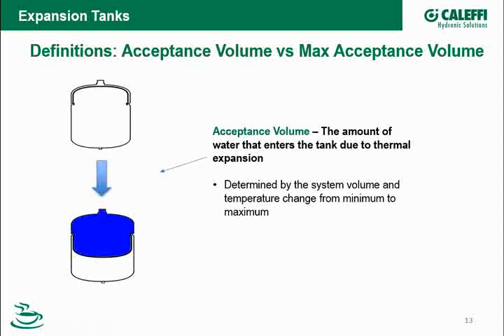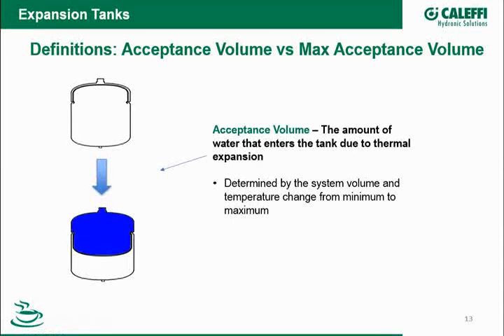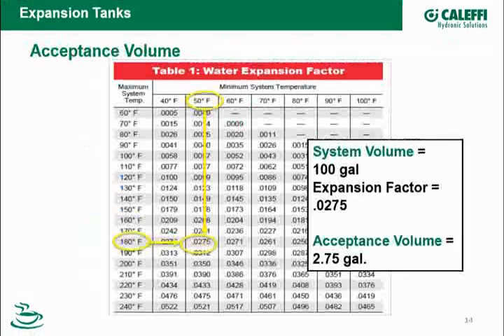Or the volume of water that's going to be generated by that expansion. For instance, this is a water expansion factor chart. Off of this chart, I look at various minimum water temperatures and various maximum water temperatures. For my example, let's say I'm heating the water from 50 degrees Fahrenheit to 180 degrees Fahrenheit. Each gallon of water through that temperature change is going to expand 0.0275 gallons. So, for instance, if I had a 100-gallon system, I have 2.75 gallons of water that I now need the expansion tank to hold.